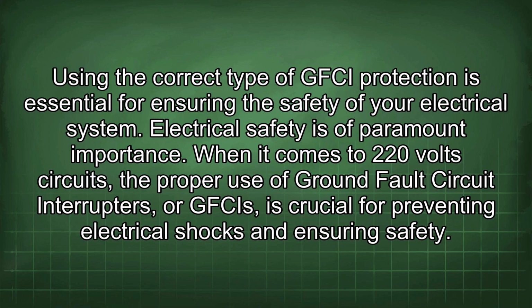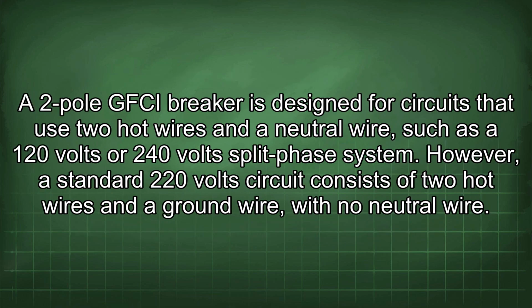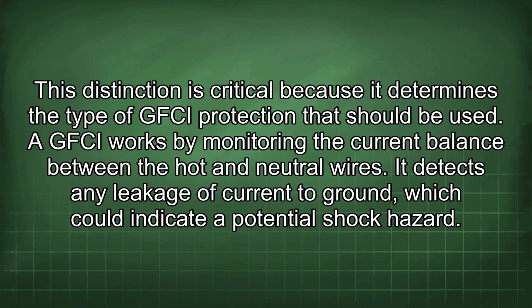Electrical safety is of paramount importance. When it comes to 220 volt circuits, the proper use of ground fault circuit interrupters, or GFCIs, is crucial for preventing electrical shocks and ensuring safety. A two-pole GFCI breaker is designed for circuits that use two hot wires and a neutral wire, such as a 120 volts or 240 volts split-phase system. However, a standard 220 volt circuit consists of two hot wires and a ground wire with no neutral wire. This distinction is critical because it determines the type of GFCI protection that should be used.